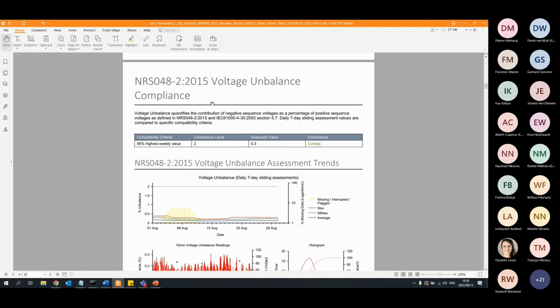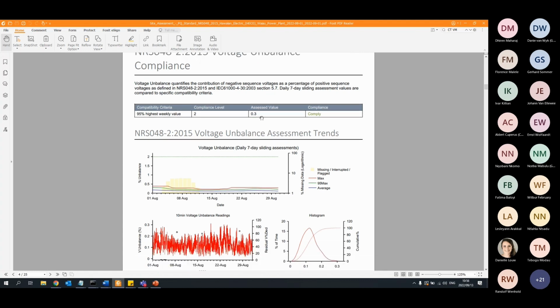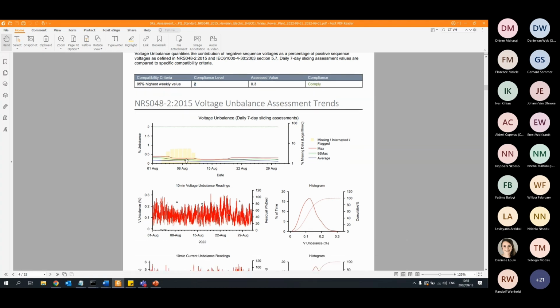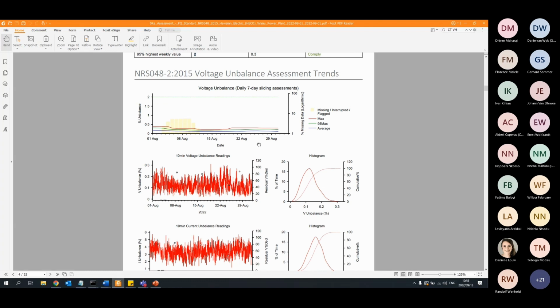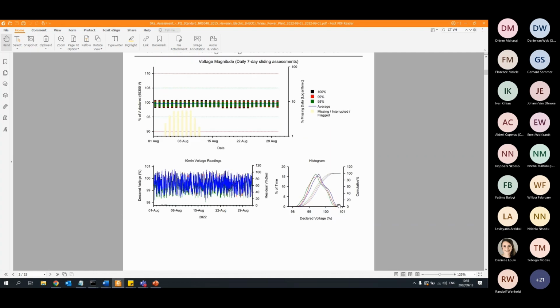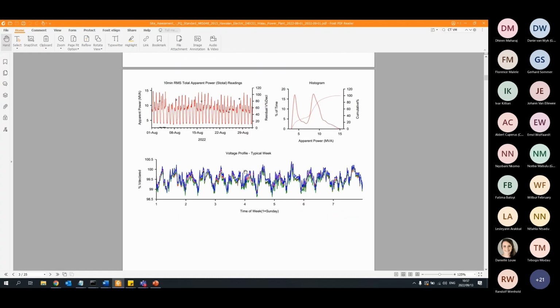All right, then we have voltage unbalance. Your highest 95th percentile voltage unbalance value, the 10-minute reading, for this period is 0.3%, and that compared to the 2% compliant limit is well below it, so it's compliant. We can see looking at the 7-day sliding assessment that it is basically permanently low. So the voltage unbalance isn't an issue, and you can also just verify that by looking at the histogram of the voltage regulation, seeing that the phases are quite on top of each other, so very accurately regulated.